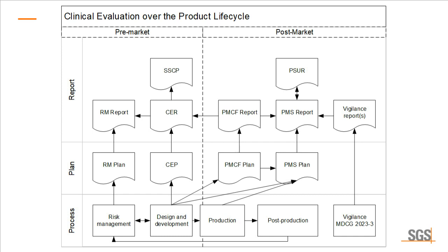So this is just the overall landscape, and everything that's marked here as documents, those are applicable deliverables for these processes, and the notified body and the competent authorities will usually want to see these unless some of these documents are not applicable for your product. But most of the time, these will all be applicable.